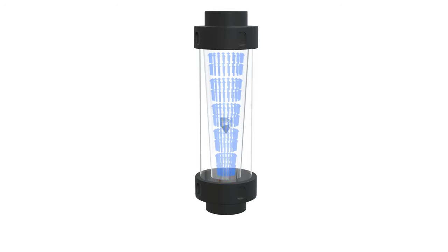Working of rotameter: When fluid flows through the rotameter, it enters the tapered tube at the bottom and the float rises upwards with the increasing flow rate. The float reaches a height where the buoyancy force equals the gravitational force and it remains in equilibrium.